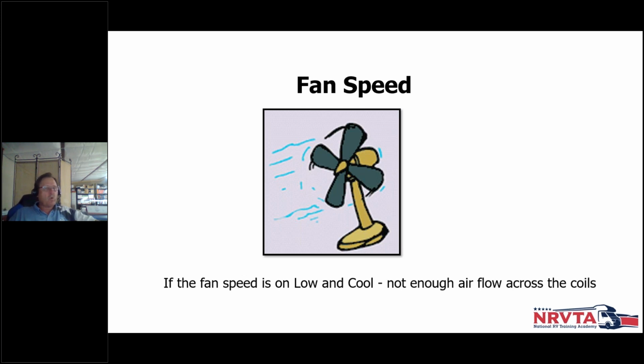So then those coils begin to freeze up. And when they freeze up, they really block the airflow. So then you either have to wait for that thing to thaw out, or you have to take a hairdryer and crawl up there and blow on those evaporator coils and melt the ice, because that's what will happen if we run these units on low speed. Now, the low speed was put in there particularly for spring and fall, when you don't need the compressor, you just need airflow coming through the air conditioner and through the ductwork.